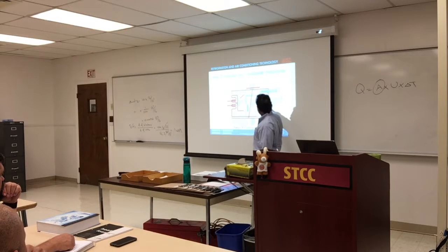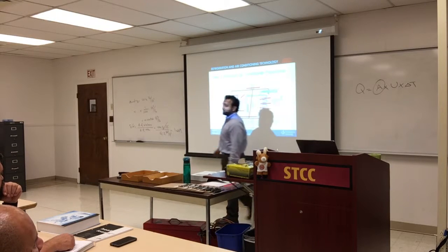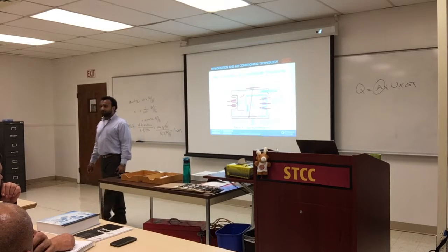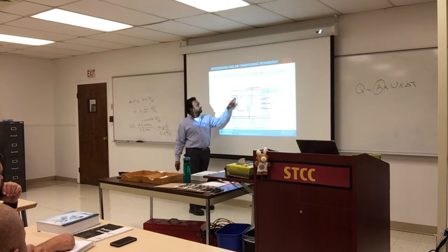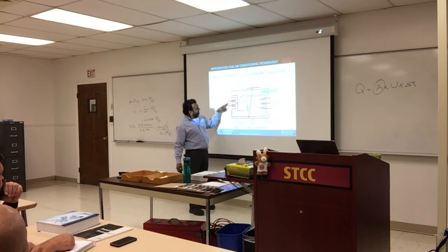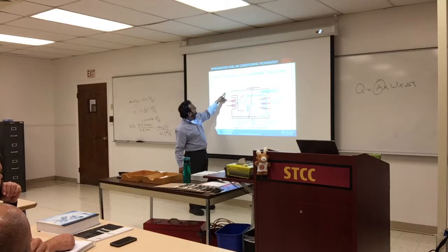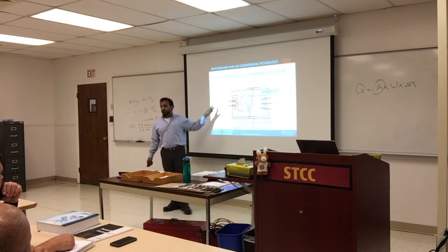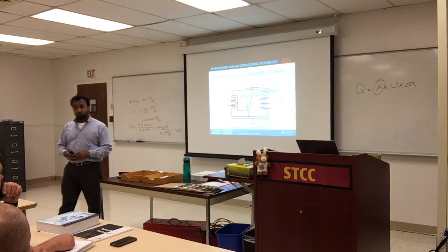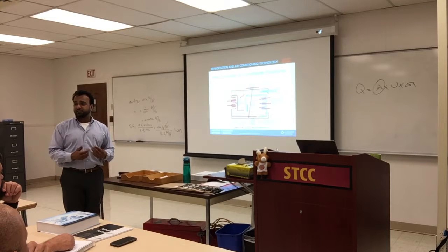And what happens to the refrigerant that has gained some heat now? It goes back to the compressor, it gets compressed. What happens when they get compressed? They get hot. So this thing gets really hot. That's why they put it in red. And it's completely hot here at the pressure of 125 at least. And the temperature now is 95 with the air outside. But this should be higher than that. So this coil is at 125 degrees and the outside is 95. So again, there's 30 degrees difference, right? That's because we want to ensure proper heat exchange.